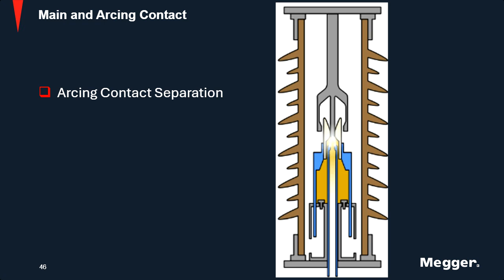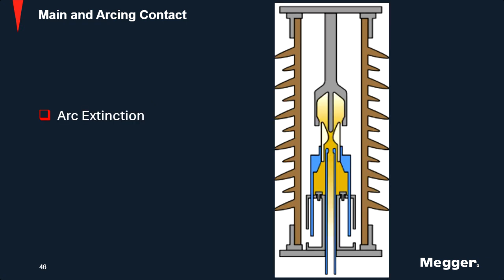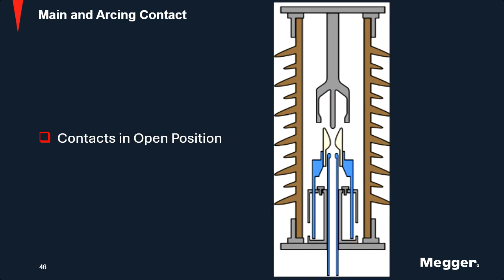As the moving contacts move down, for SF6 or for oil, as it moves down in this tube right here, gas or oil is forced up into it to help extinguish that arc from the arcing contact. And obviously, once the arc is extinguished, the breaker comes to the open position. So when you're doing DRM, you're measuring this contact right here, your arcing contact on your stationary contact.